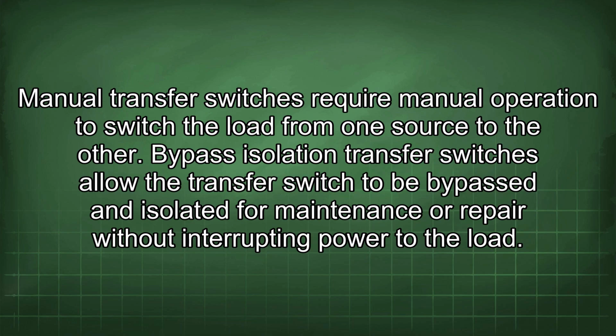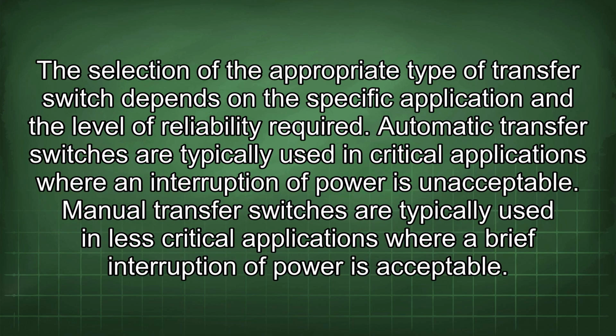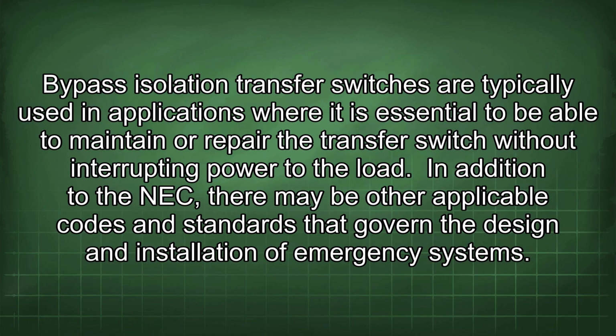The selection of the appropriate type of transfer switch depends on the specific application and the level of reliability required. Automatic transfer switches are typically used in critical applications where an interruption of power is unacceptable. Manual transfer switches are typically used in less critical applications where a brief interruption of power is acceptable. Bypass isolation transfer switches are typically used in applications where it is essential to be able to maintain or repair the transfer switch without interrupting power to the load.